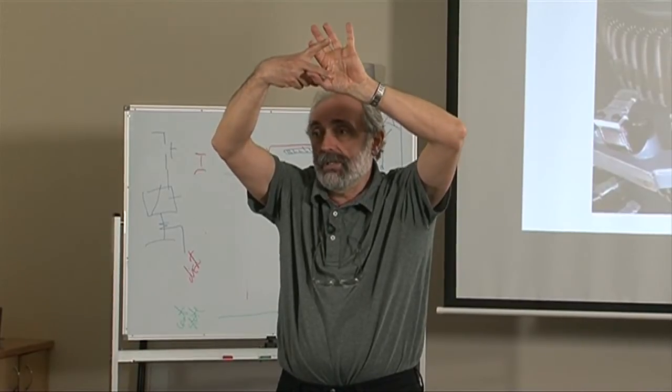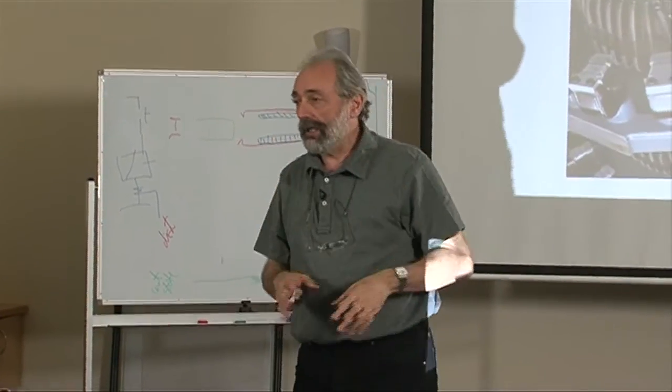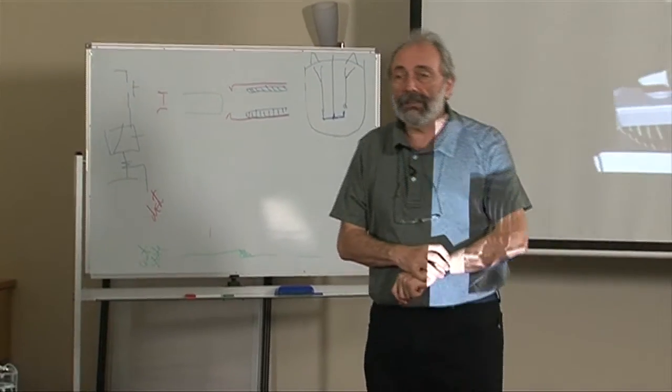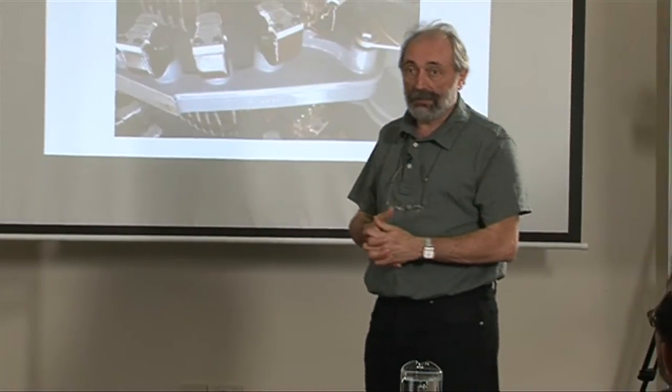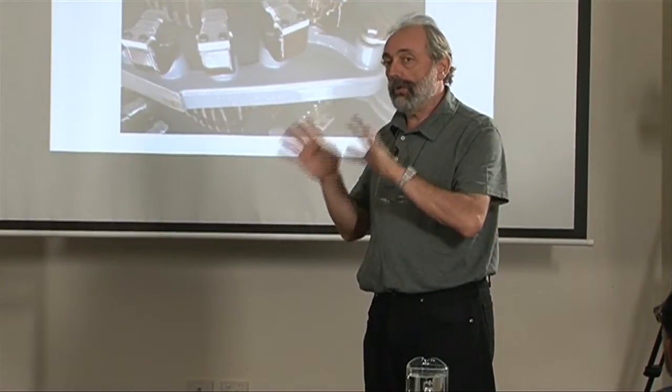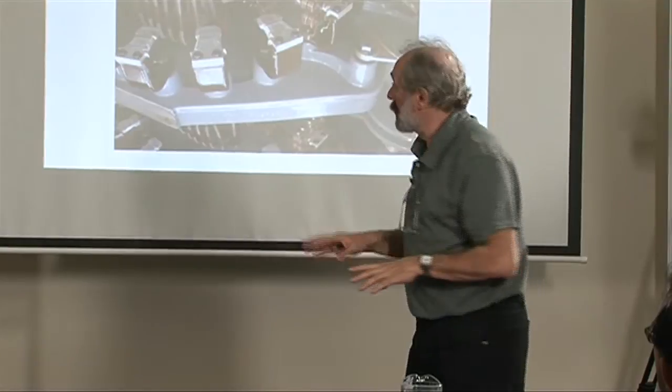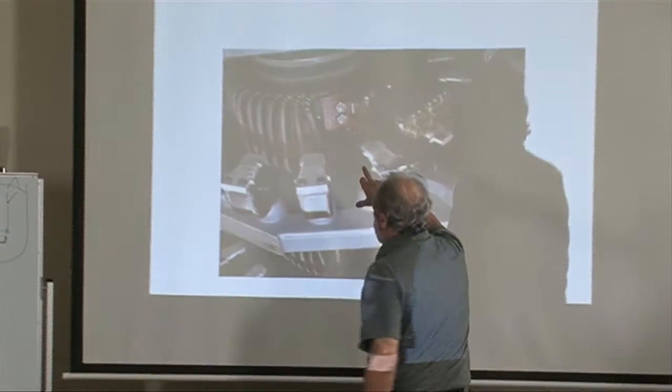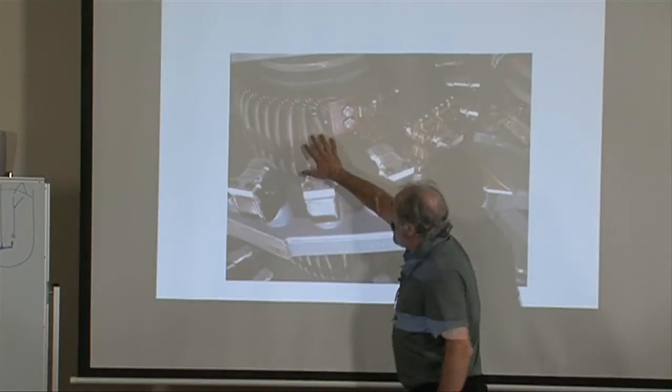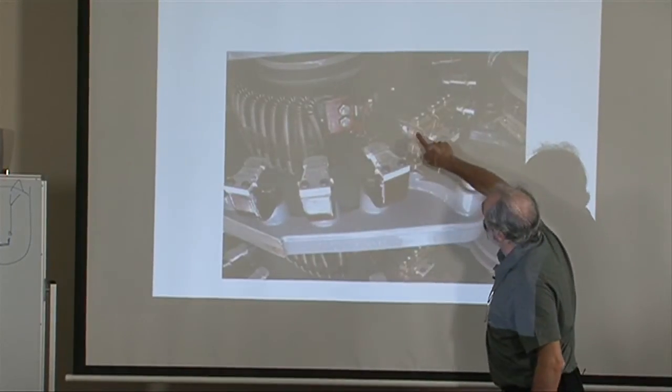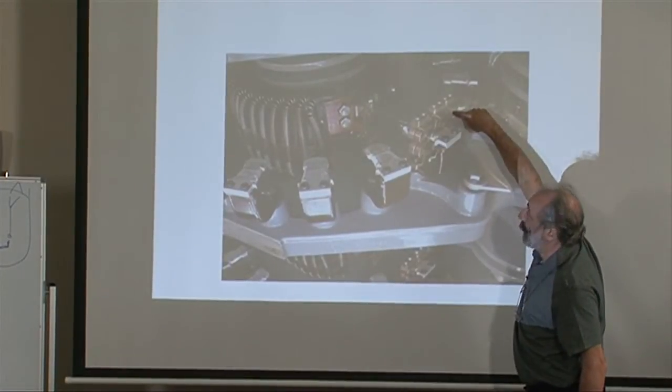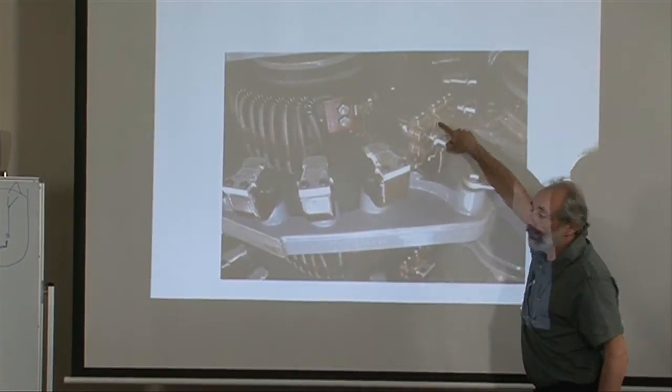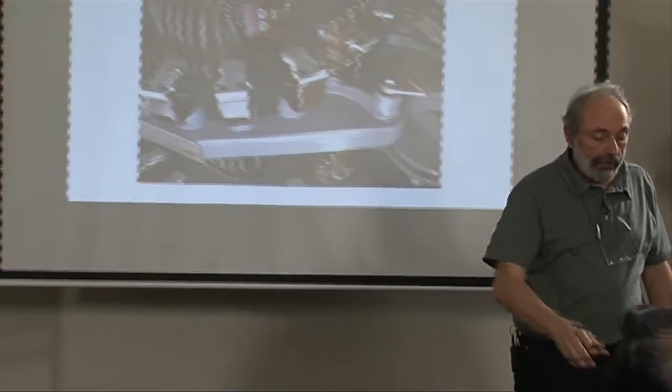You put resistors. In America they put reactors. It's called preventive auto transformer. It's a reactor that does the same thing as resistors. And I understand even in Australia there are some reactance tap changers. But we're going to concentrate on resistance types. So here is my resistor. This resistor is connected with this roller. And that resistor here is connected with the third roller. The middle roller is the current carrying one.